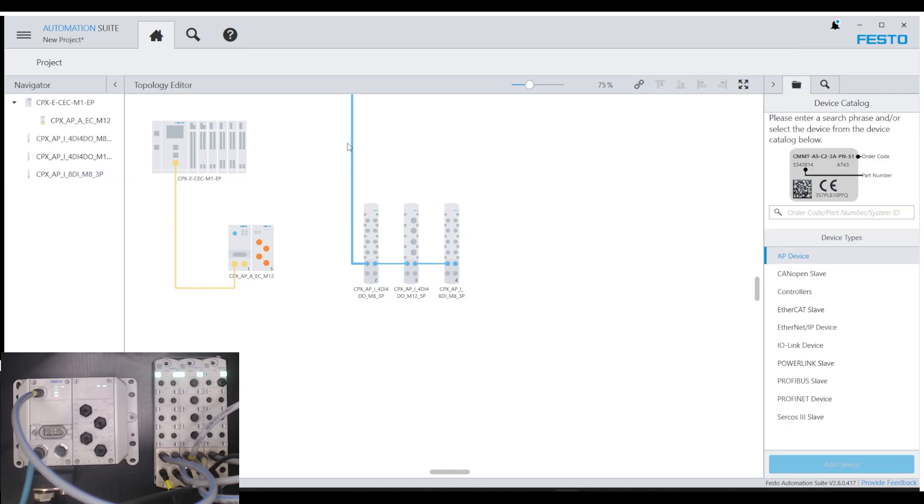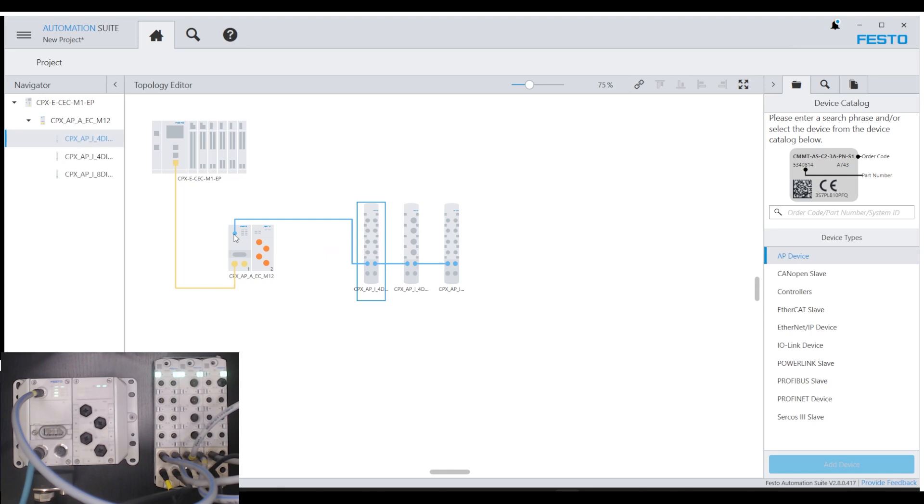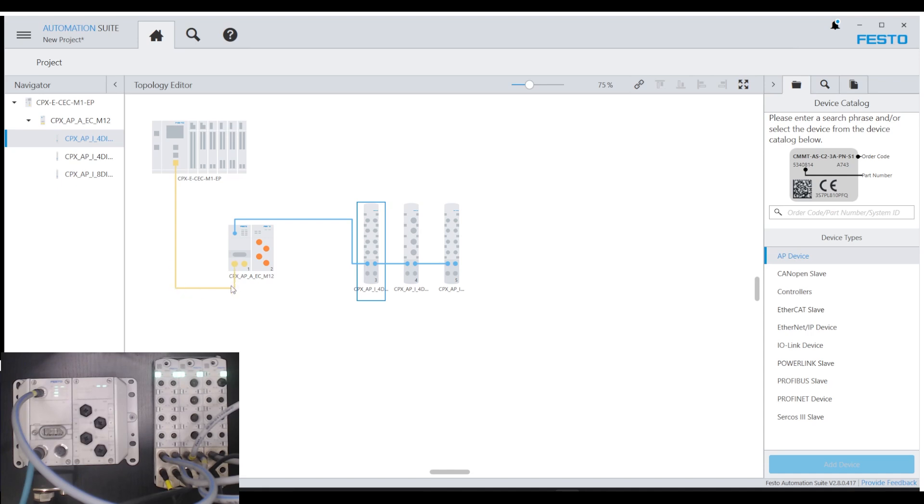Notice that it brings in all the devices. There is one small correction I have to make here. I delete this erroneous wire going to the first API module, and I'll reconnect that. And now you can see my topology that's both in the topology editor as well as on the left hand navigator matches what I have in the field. You have the CPXE rack here, and you can see the yellow connections are the EtherCAT field bus going to just that first node. And then from the blue port, that AP technology port allows me to connect those API modules far out in your machine.